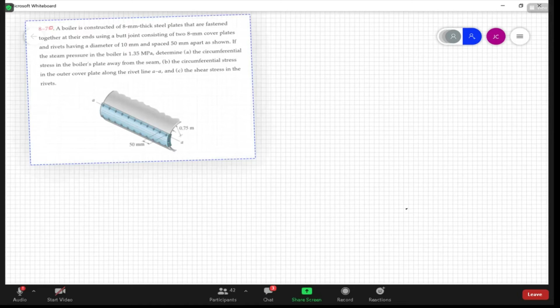And then there's a double plated seam here. I'm writing over it, so now it's impossible to see. There are two plates that are riveted together through the bent center plate, and that closes off or seams up the boiler. Now, they give us the thickness of the plate. The boiler bent plate is 8 millimeters, and the covering gusset plates are also 8 millimeters. And the rivets are given a diameter of 10 millimeters and spaced 50 millimeters apart.